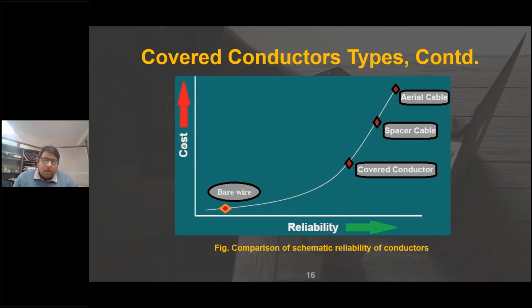So if we see a comparison of schematic reliability of conductors, you can see that the bare wire, although it has less cost, is also susceptible to less reliability. If we see the covered conductor, its cost is comparatively high if you look towards your y-axis and then move towards the x-axis, so the reliability is much greater than bare conductors. But as you move to the spacer cable and aerial cable, the higher counterparts of the covered conductor, the cost gets high, and so does the reliability. So the covered conductor is a sort of trade-off between these high-end counterparts and the low-end bare wire, because at a fraction of the cost it gives much better reliability as compared to bare wire, which is basically in use today.